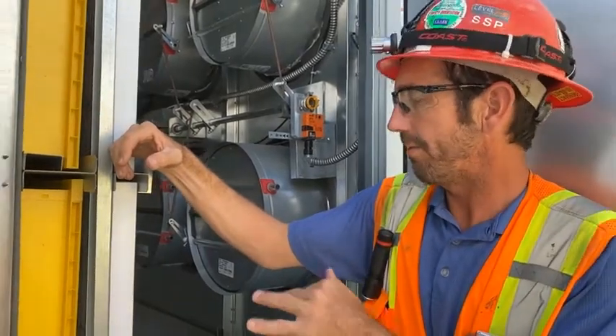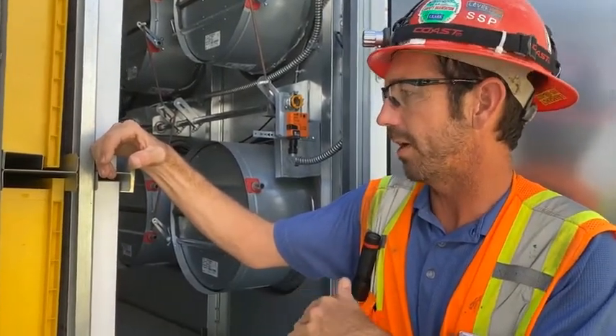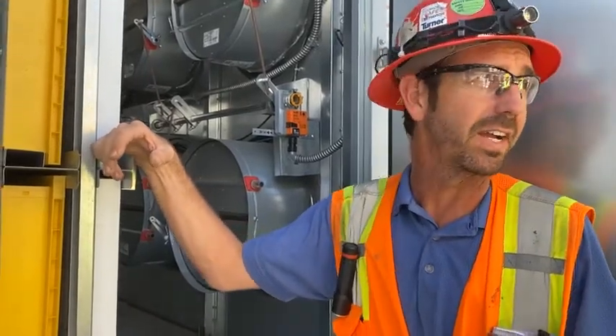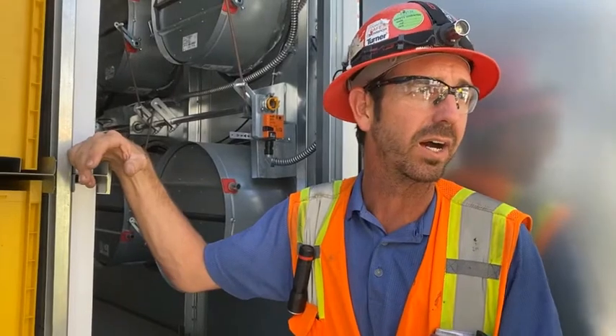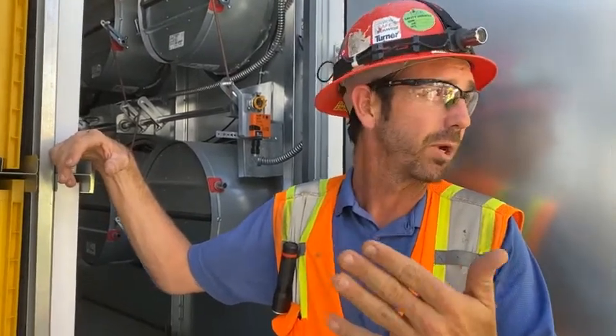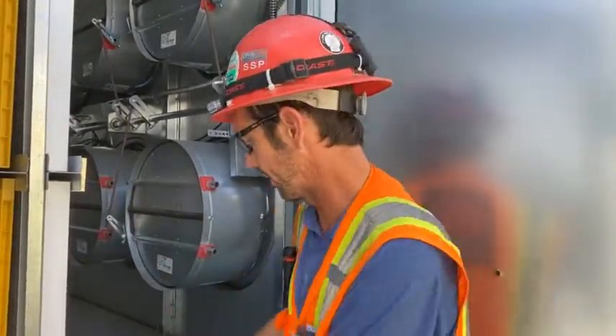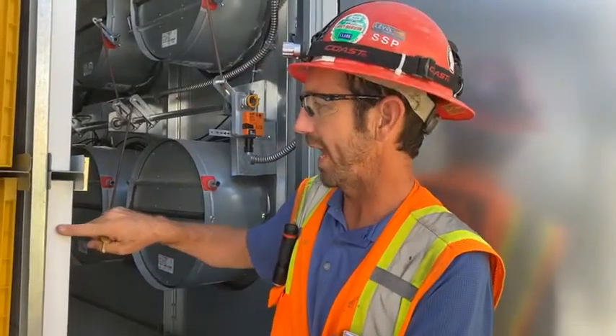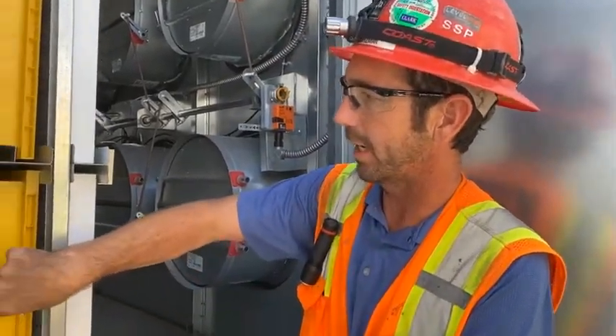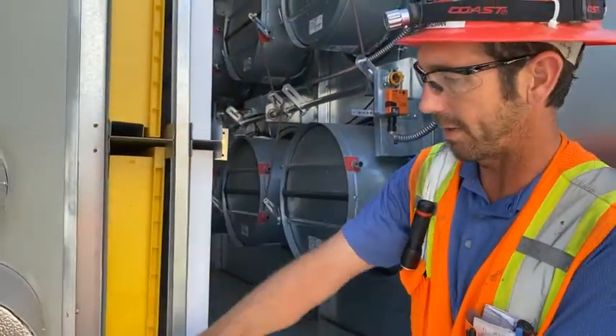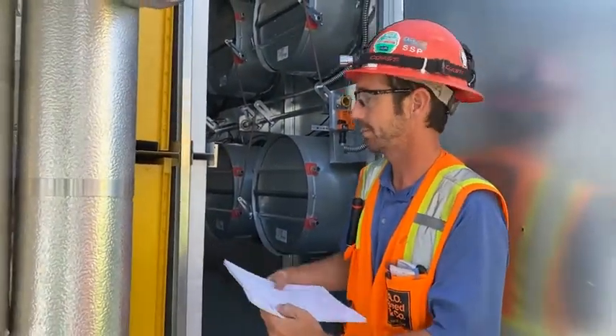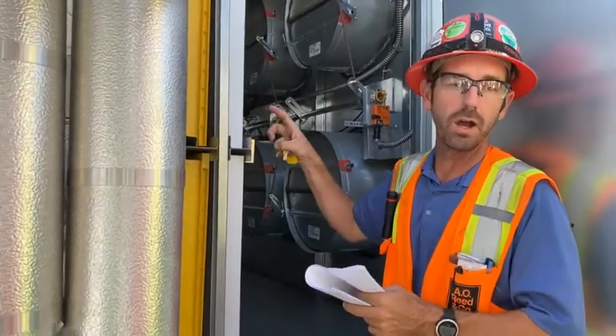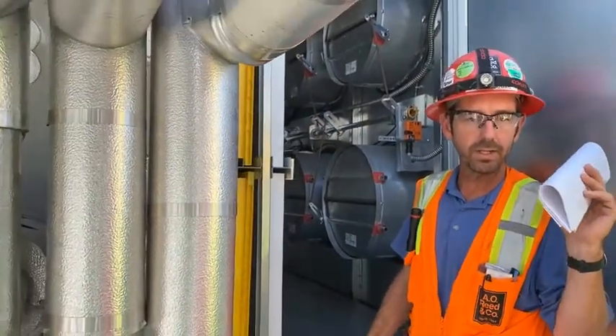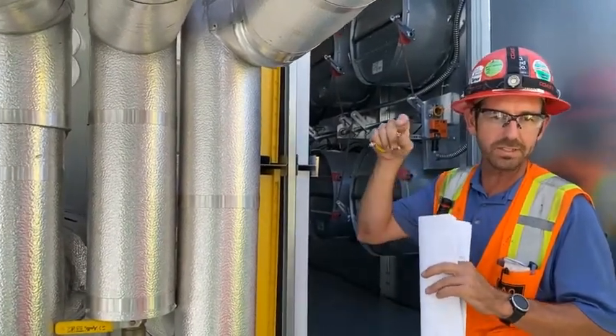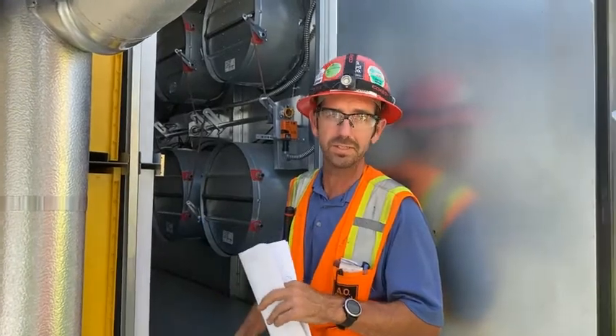We'll want to reference the documentation with the filters as far as the maximum pressure drop across the filter. Every manufacturer is different, so we need to use that information to go by for the maximum pressure drop across the filter. Okay, it just depends on different manufacturers and the different style of filters. But we have a MERV 8 2-inch filter here, MERV 13 4-inch filter here. Cartridge style right now, you can remove this panel and put a box filter in. The filter sizes are on my startup sheets and on the front of the unit. On the front of the unit, it's just missing the last digits. The top filters would be a 2-inch, the bottoms would be the 4-inch filters. Okay.